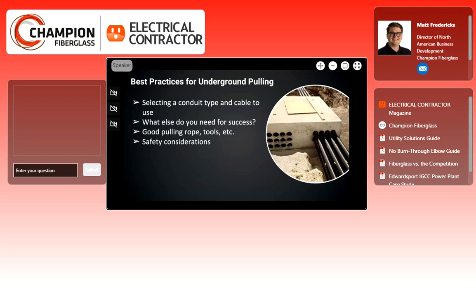Best practices for underground pulling: selecting the conduit type and cable to use is probably one of the most critical things to focus on. Looking at the coefficient of friction between the cable and the conduit can help you keep pulling tension down and pull further.